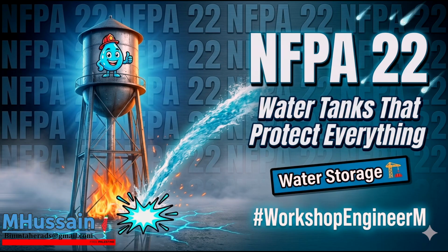If a fire starts underneath that suspended horizontal tank, say, a pile of oily rags or a pump motor catches fire, the ceiling-mounted sprinklers cannot reach the flames. The massive footprint of the tank blocks the downward water spray, creating a dry shadow. The fire will grow unobstructed beneath the tank, directly heating the FRP material. Therefore, the engineer must design an entirely separate array of sprinkler heads underneath the tank to protect that shadow area.